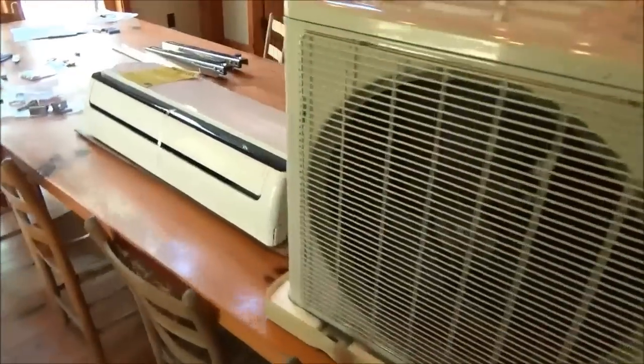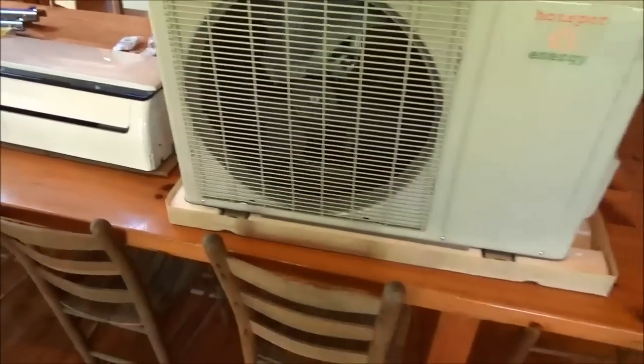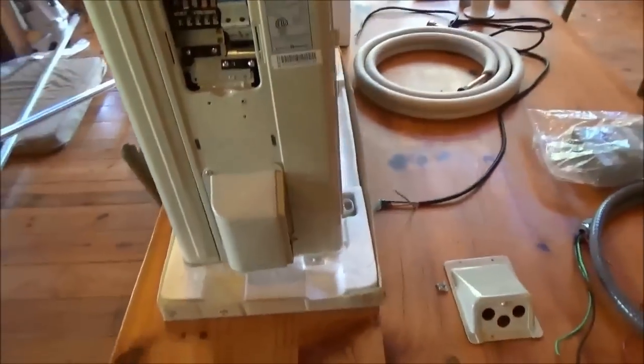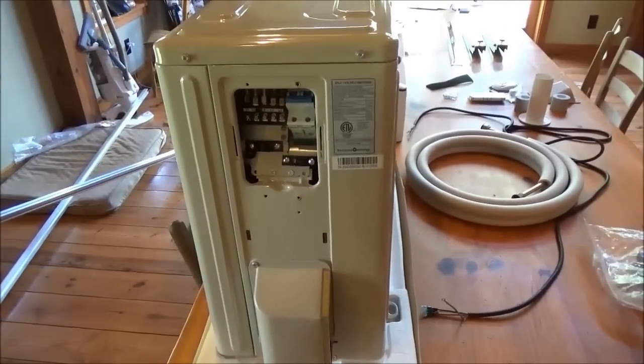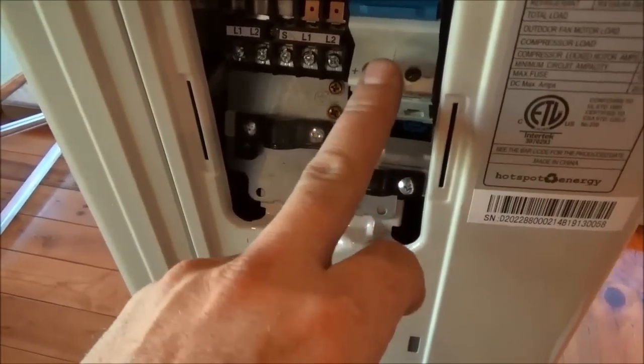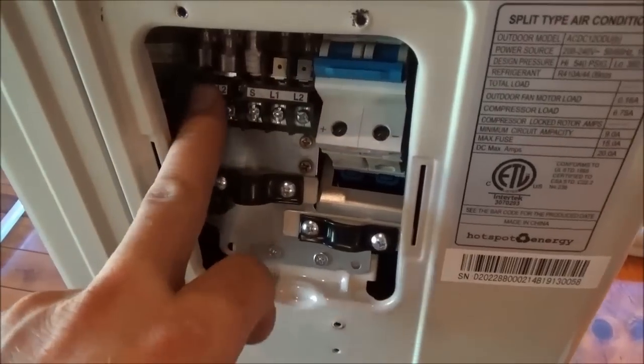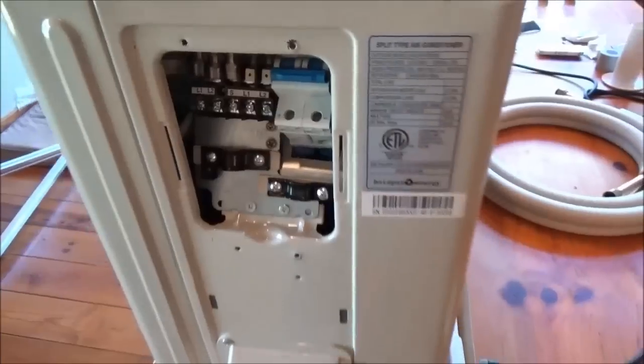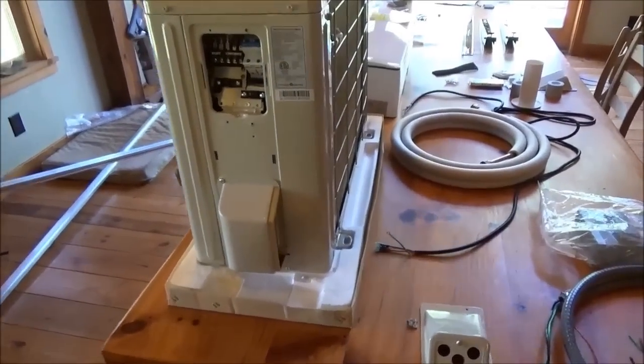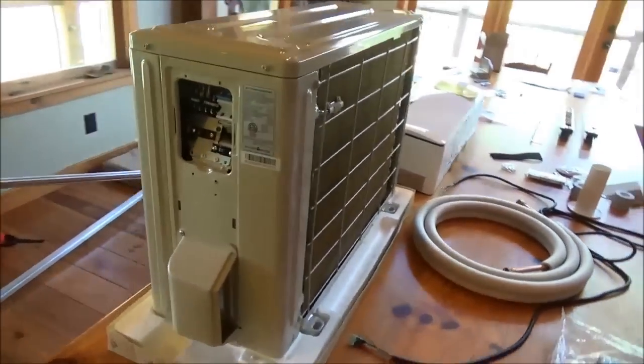This is a one-ton mini split heat pump, but the cool thing is that it uses solar energy — it's a hybrid, using grid and solar. We're going to be hooking up our solar panels to this breaker, then the inner fan coil hooks in here and then house power. This will take about 800 watts of solar to run the DC compressor inside the unit.